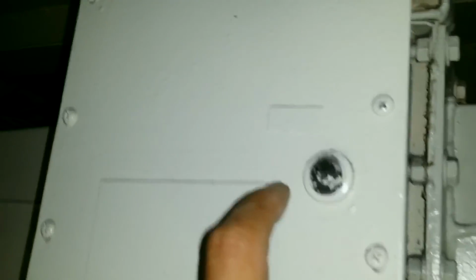Here we've got a ventilation heater. So ventilation heaters have two cables. One is the 440 coming in from the contactor to energize the actual heater that is inside there. The other cable is just a two-conductor cable that goes to the switch. By the way, that is the thermostatic switch, or over-temp switch, should I say. Whenever that switch trips, this is the reset for it. You have to press it really hard to be able to reset it.